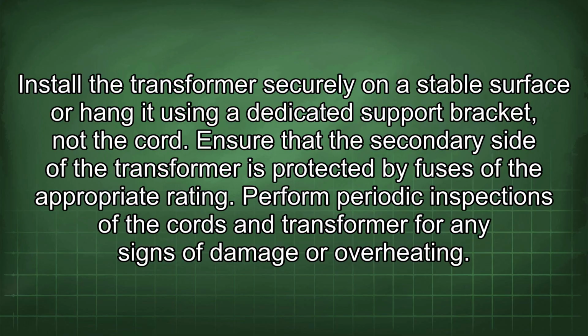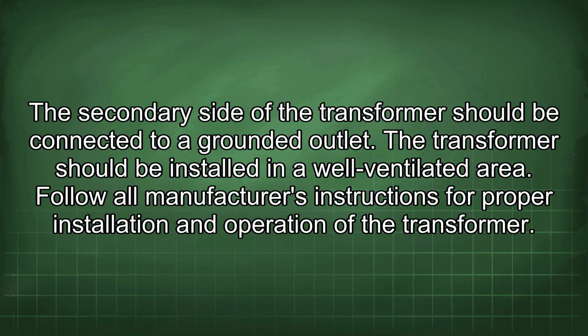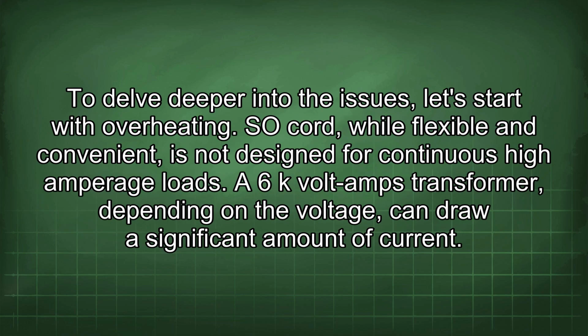Perform periodic inspections of the cords and transformer for any signs of damage or overheating. The secondary side of the transformer should be connected to a grounded outlet. The transformer should be installed in a well-ventilated area. Follow all manufacturer's instructions for proper installation and operation of the transformer. To delve deeper into the issues, let's start with overheating.